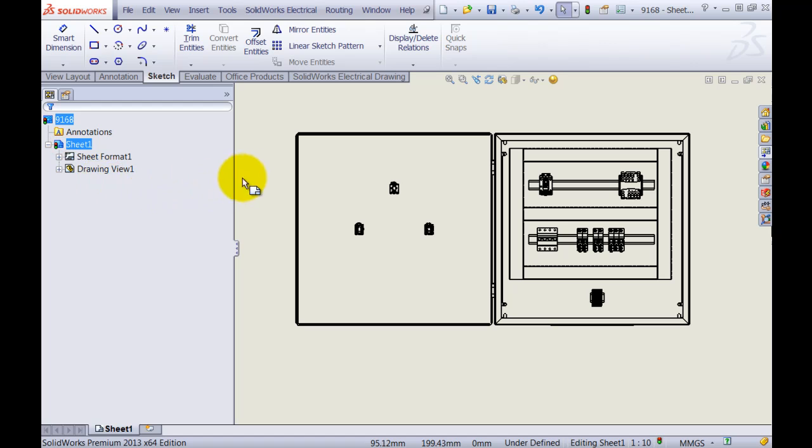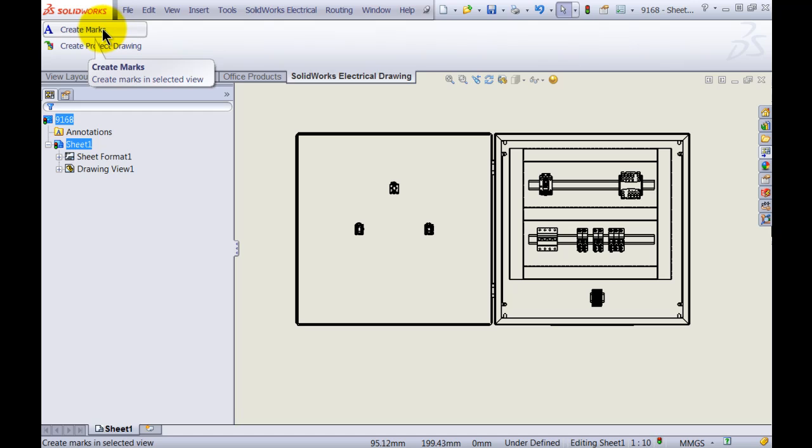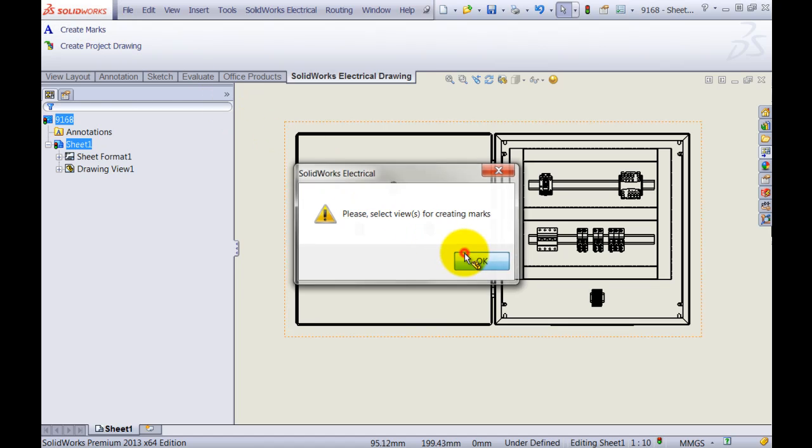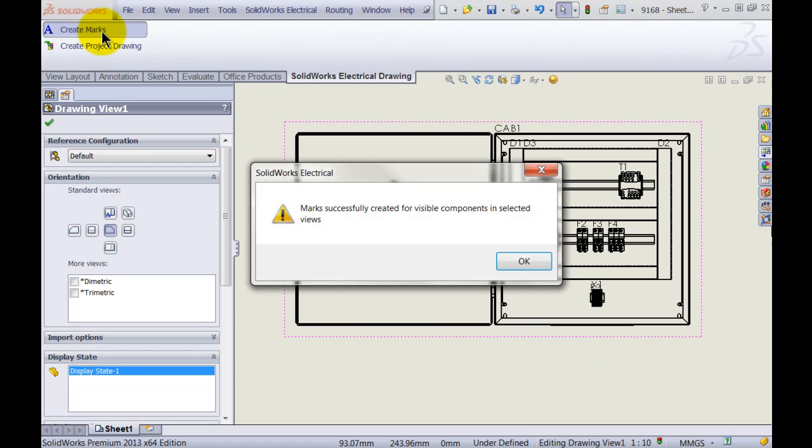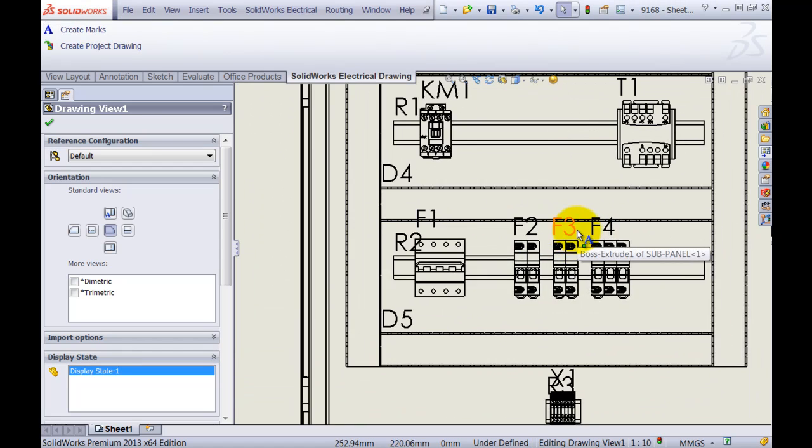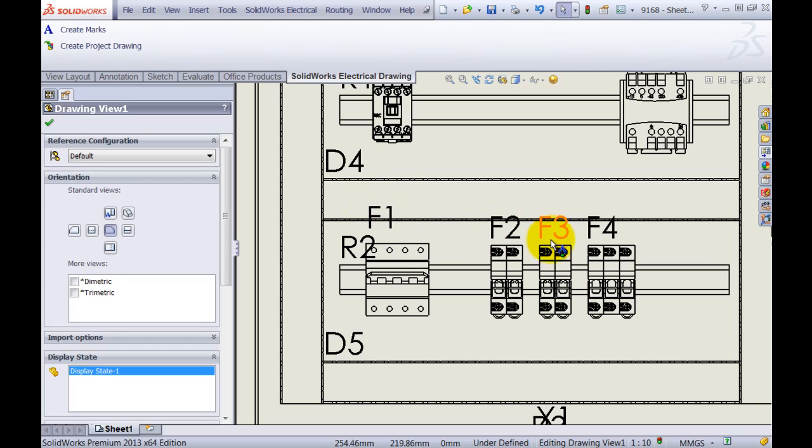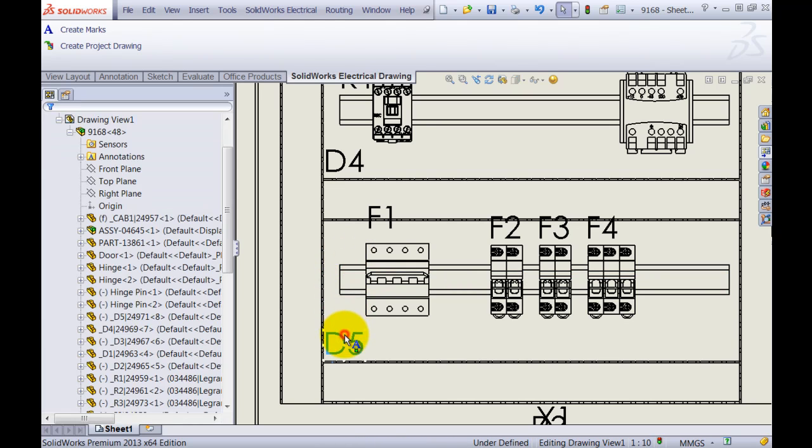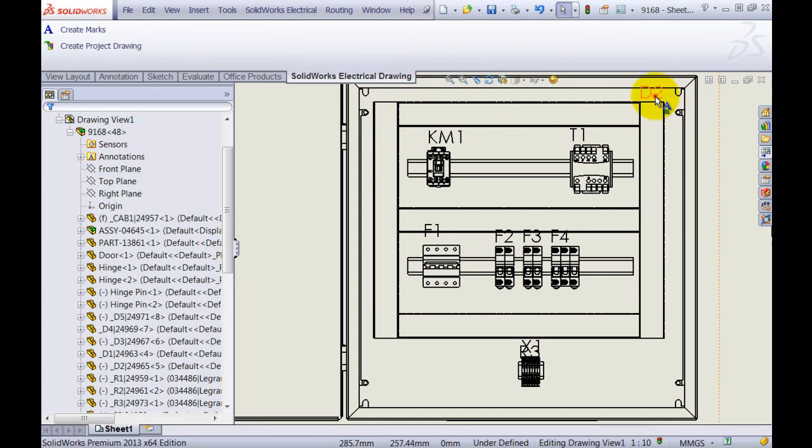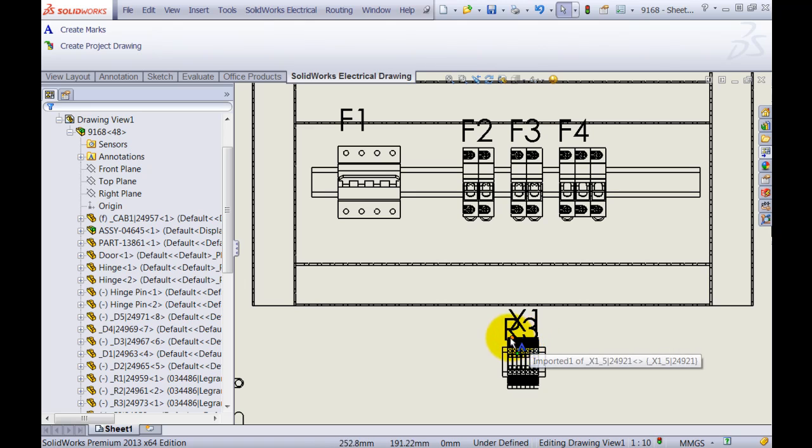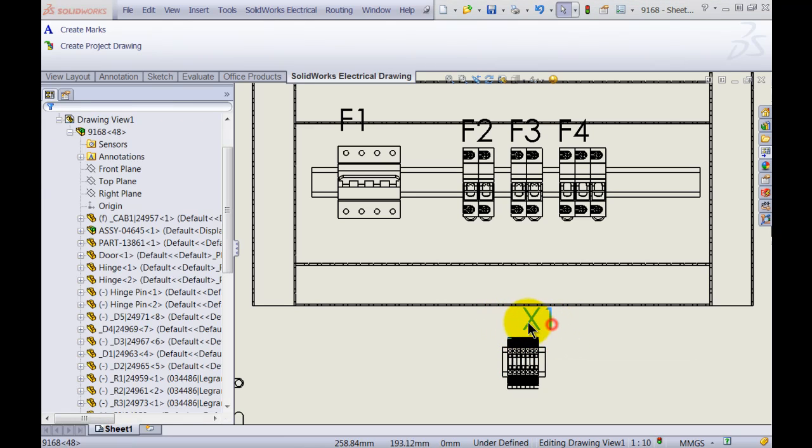For now I'm just going to show you a couple of electrical commands that we can do here. We can let SolidWorks Electrical automatically create marks for each component. So if I create mark, of course I need to select the view first. What it will do is it will automatically fill in F1, F2, F3, F4. It will also do the things for the rails and for the ducts. But if you're not interested you can just simply delete the ones for the rails and the ducts if it creates too many marks. Let's see if I can get the R3 gone. Here we go.